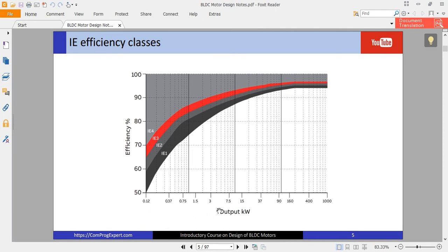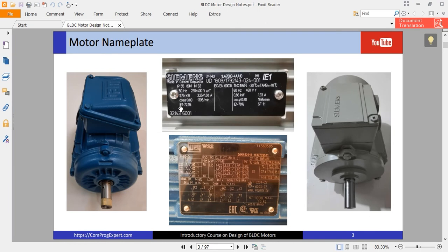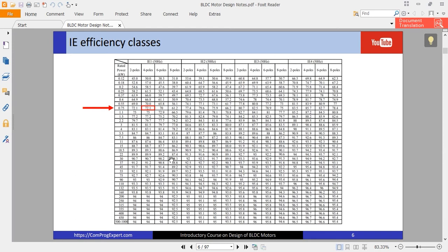As you can see, when the output power of the motor is higher than 3 kilowatts, the efficiency for all classes should be higher than 80%. Our motor is at 0.75 to 1 HP, and for the IE1 efficiency class it should be higher than 70% — around 72%. If you see the efficiency number for the Siemens motor, it is 72.1%. You can use this table to see the efficiency of the motor for different efficiency classes versus the output power and the number of poles. Our motor is a 4-pole induction motor at 72.1%.